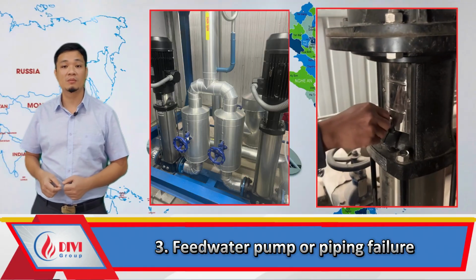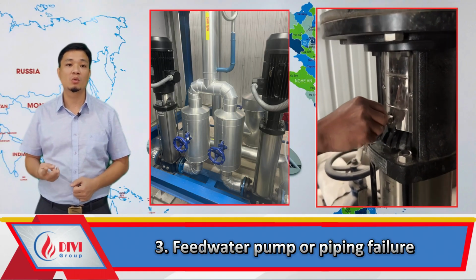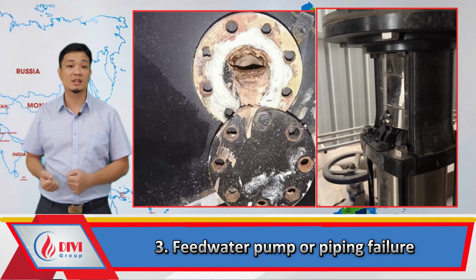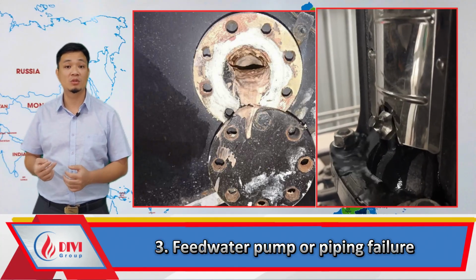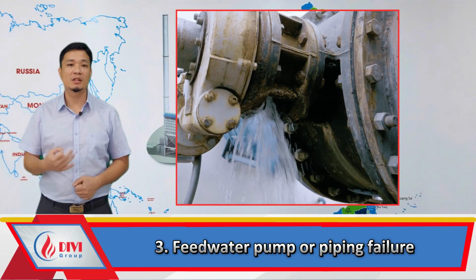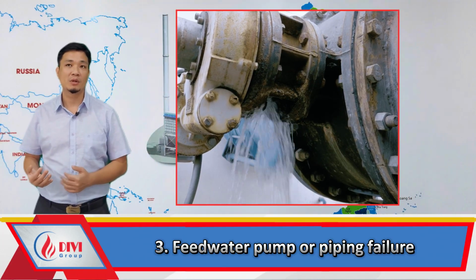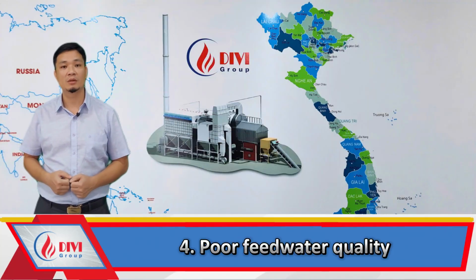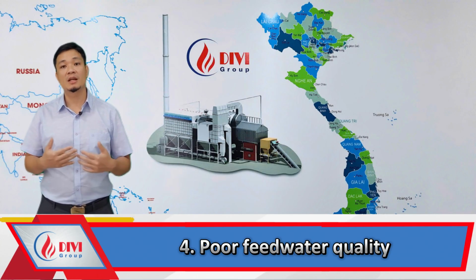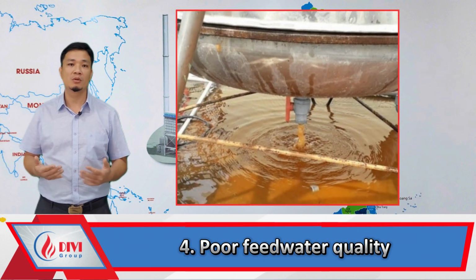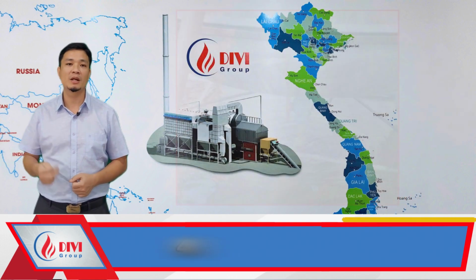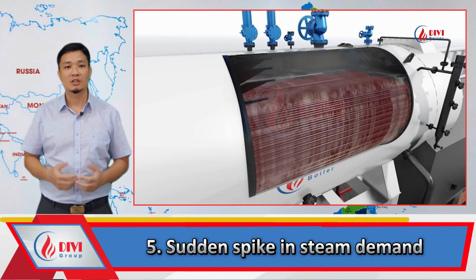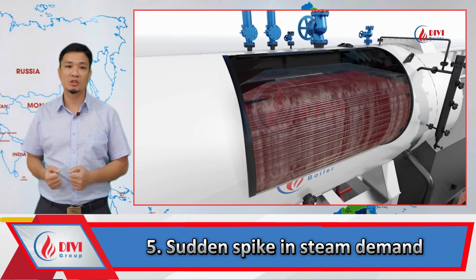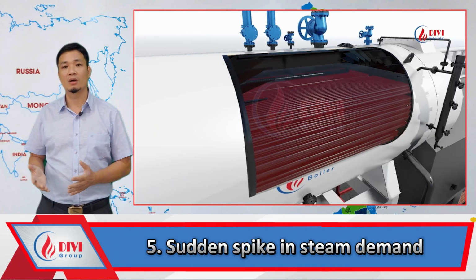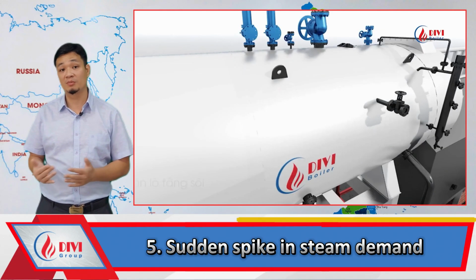Feed water pump or piping failure: feed water pump motor failure, blockage in feed lines, or heavy scaling in economizer. Entirely dependent on auto mode without manual checks. Example, leaks in economizer tubes can prevent feed water from entering the boiler. Poor feed water quality: high total dissolved solids, TDS, or suspended solids leading to scale deposits and blockages. Sudden spike in steam demand: increased steam consumption without sufficient feed water compensation causes rapid level drop. There are other possible reasons, but these are the most prevalent.